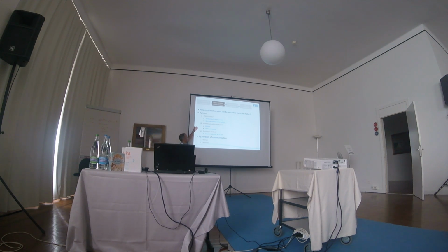Somebody could try to convince us to use a communication protocol. But this is a problem. Why? Because communication protocols are usually battery consuming. When you interrogate the meter, it will use a lot of battery, and they are very slow, so we will not be able to read the meter with a very high frequency. The good thing about using a protocol is that the meter tells you the exact reading with all the numbers.